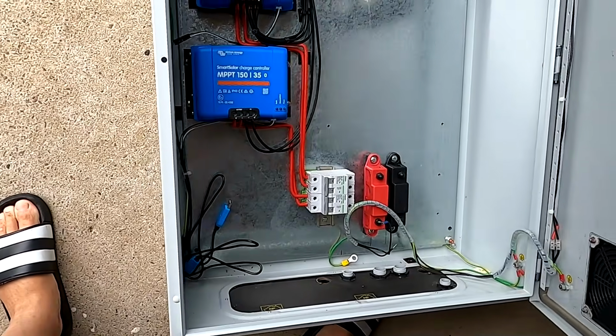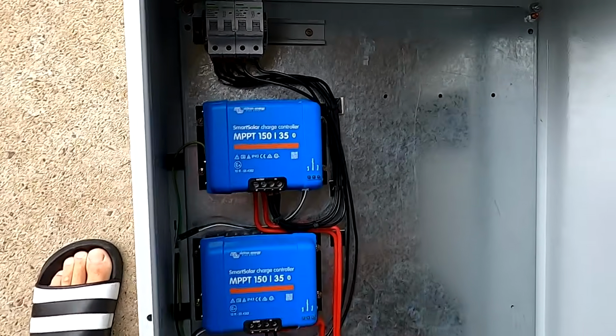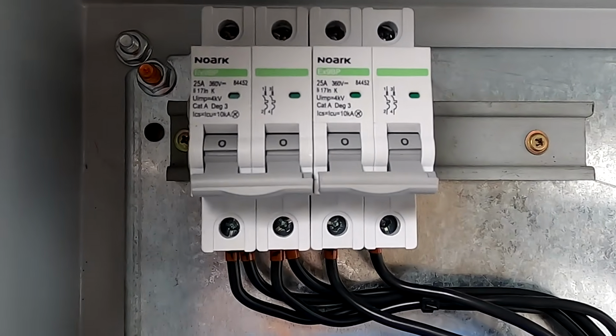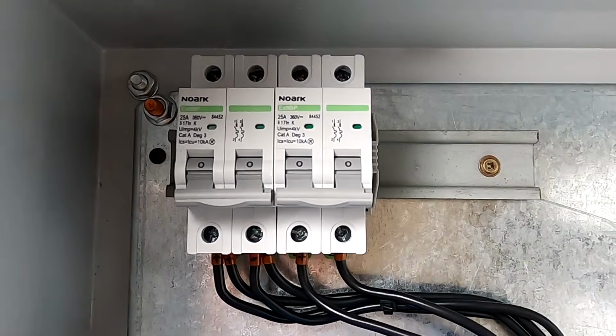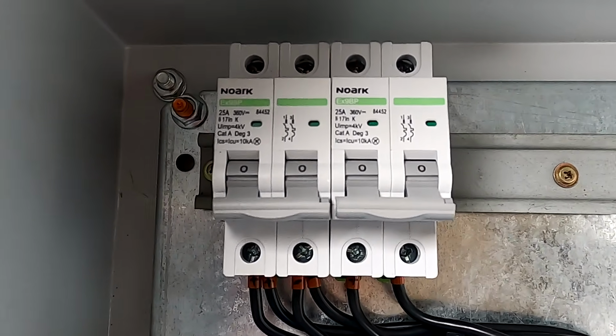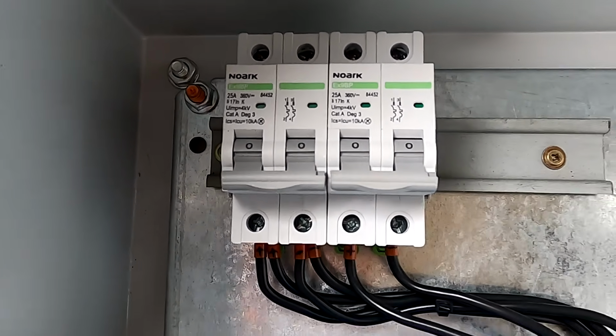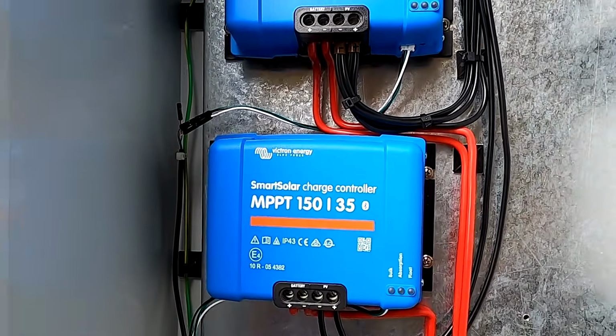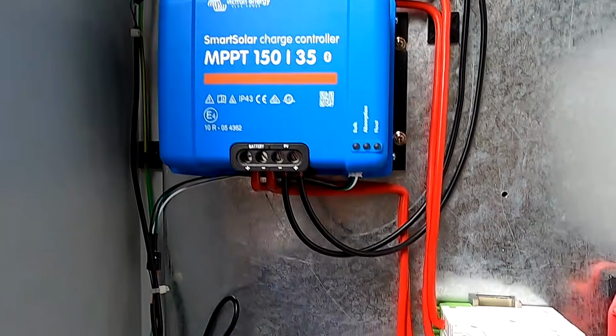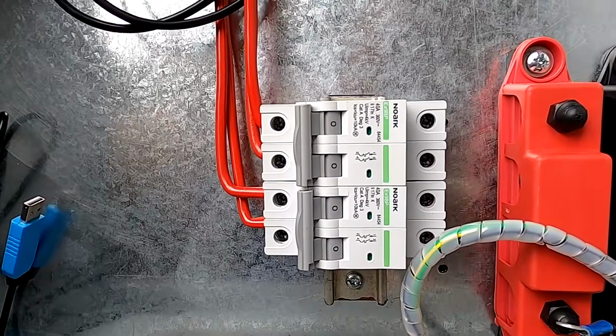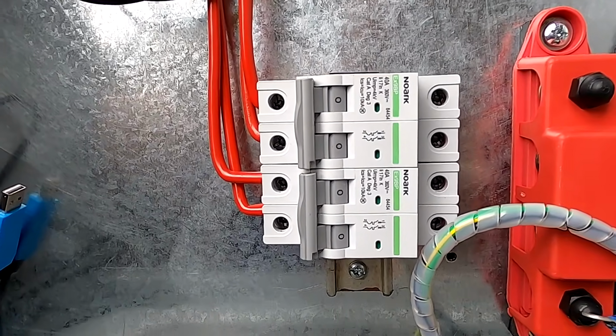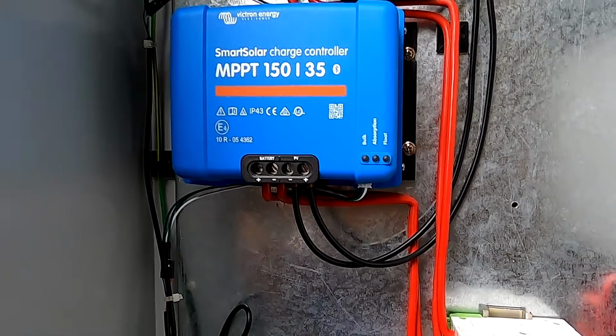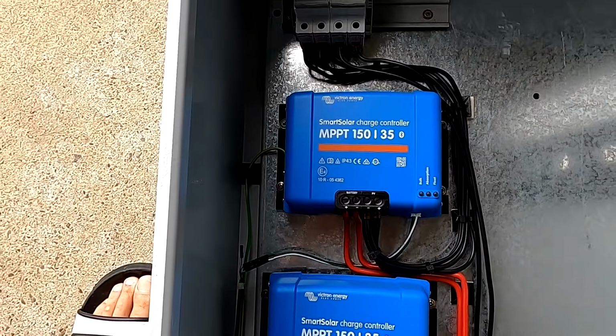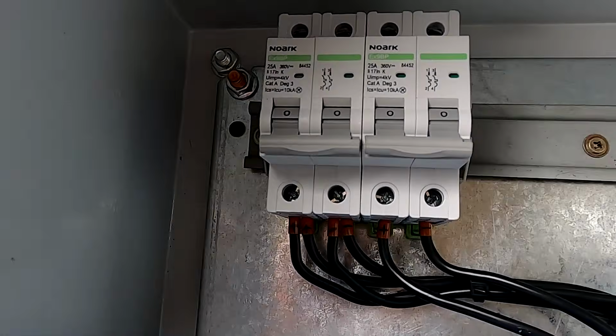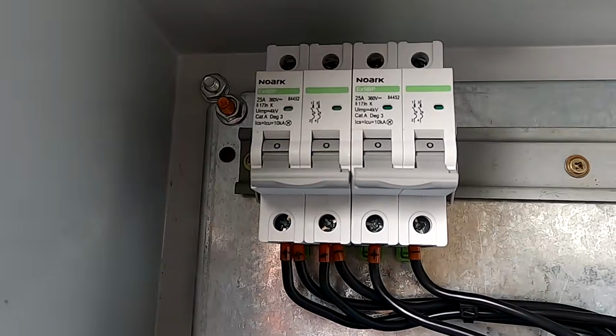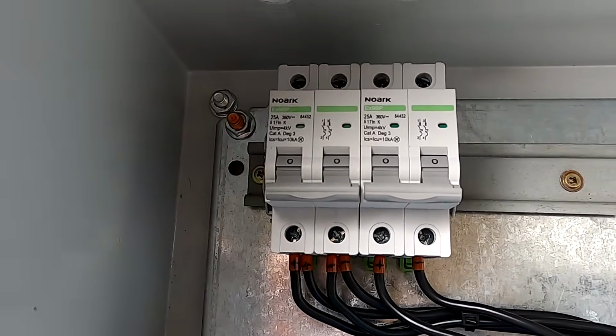If you remember the old installation in the electrical cabinet, we had these circuit breakers DIN rail mounted up here, right? This disconnected our east and west roof before they actually hit the solar charge controllers. Then we had DC fusing, or isolators again, at the output of the solar charge controllers, so we could completely isolate them. This was a quick flick of the switch to disconnect the whole east roof.